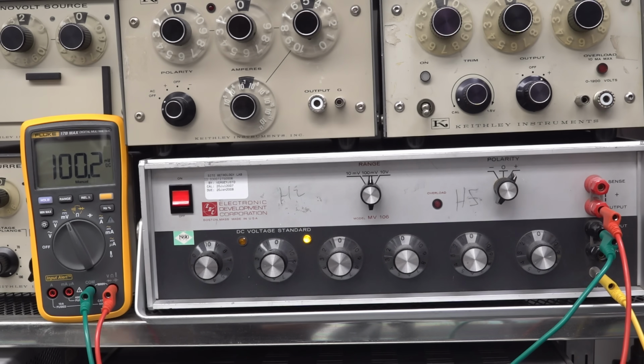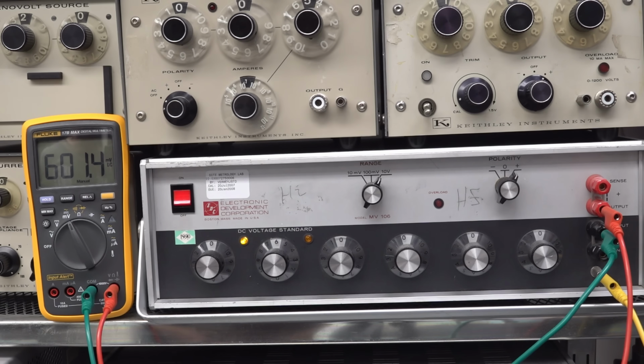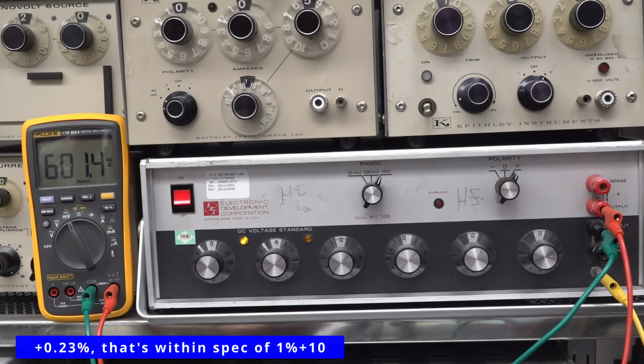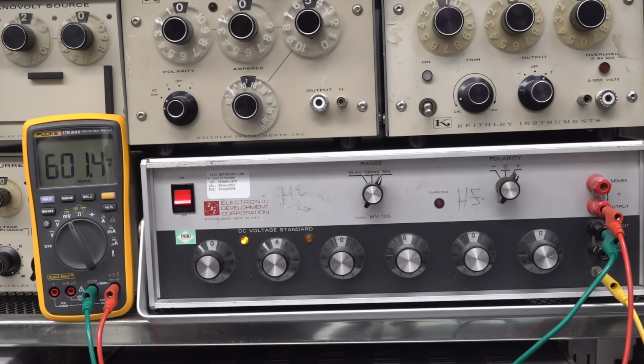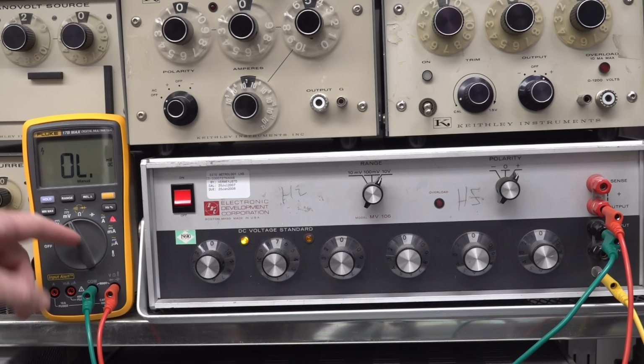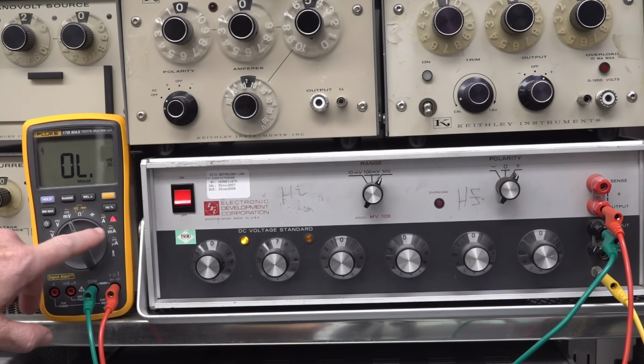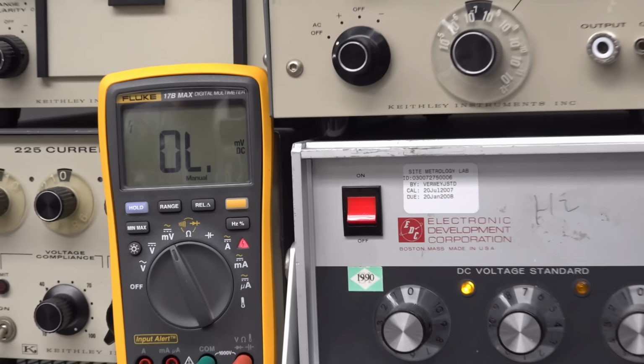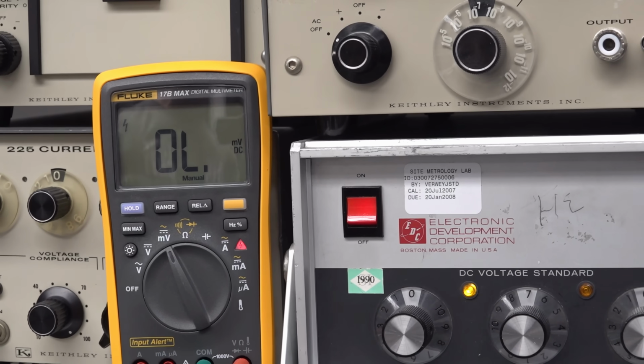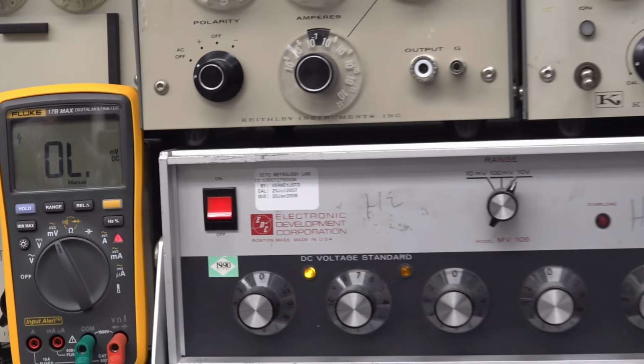100 millivolt, not quite bang on. Oh, it's a bit out on 600 millivolts there. 1.4 above, but yeah, that's like more than half within specs, so okay. But check this out. This is nuts. If I go up to 700 millivolts, okay, it's over range because it's 6,000 count, but the high voltage, what I thought was a high voltage warning indicator came on. It's not. It's an overrange indicator.